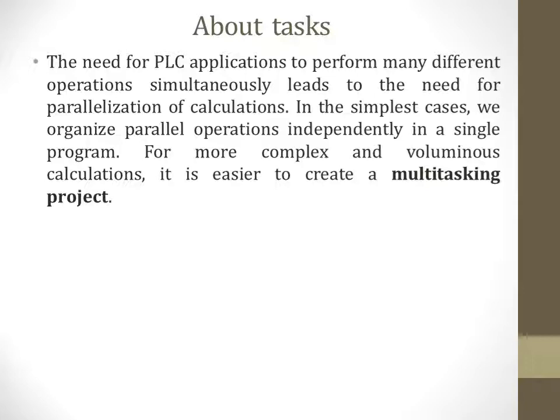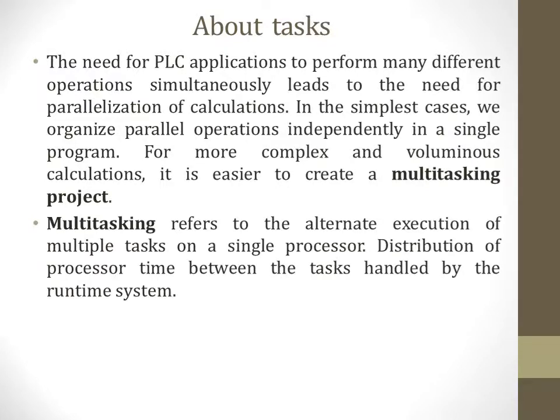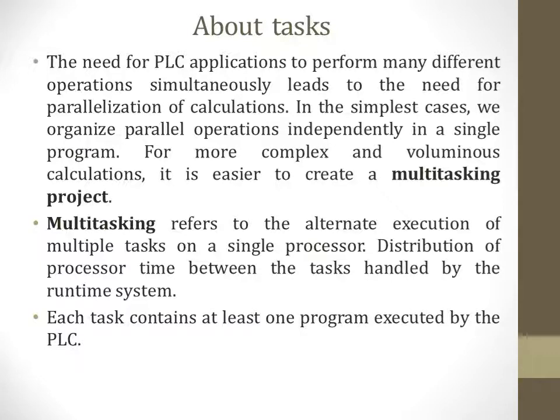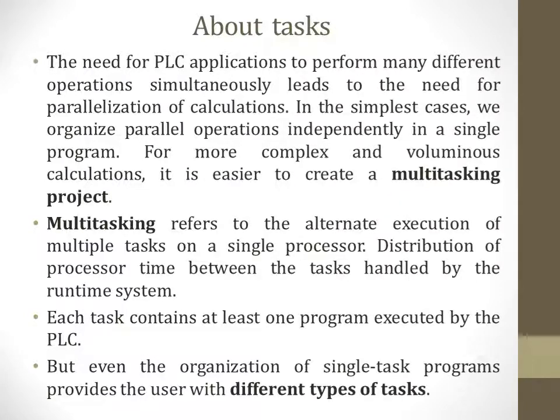For more complex and voluminous calculations, it's easier to create a multitasking project. Multitasking refers to the alternate execution of multiple tasks on a single processor. Distribution of processor time between the tasks is handled by the runtime system. Each task contains at least one program executed by the PLC.